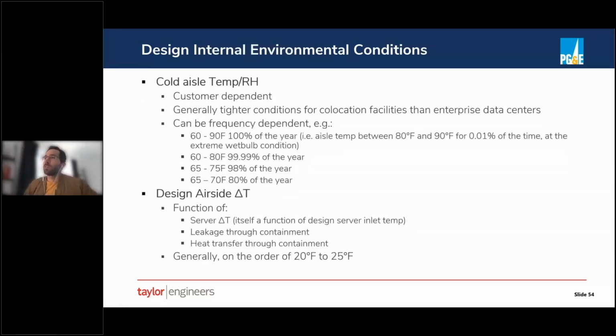we just kind of touched on some considerations for the design ambient conditions, but we also need to consider the design cold aisle temperature and RH conditions. As Jeff talked about earlier, the most important thing is the temperatures entering the pizza box, not necessarily the temperatures leaving the pizza box, because they internally have fans, at least for an air-cooled server, that are dynamically modulating speed in order to make sure that chip temperatures are staying where the manufacturer wants them.